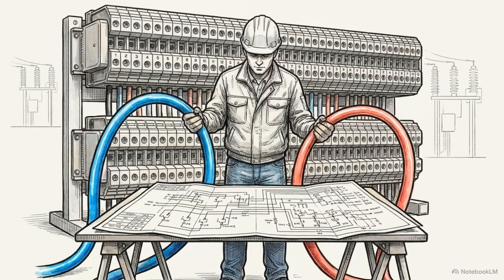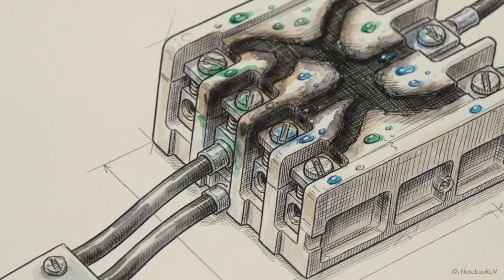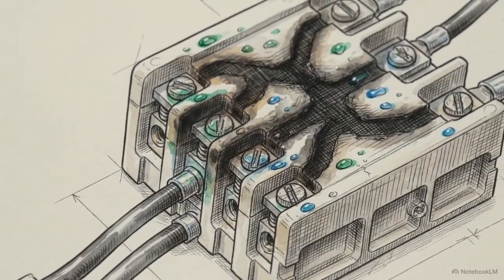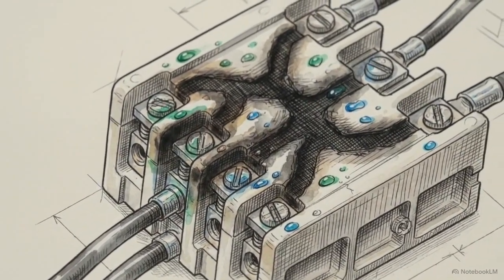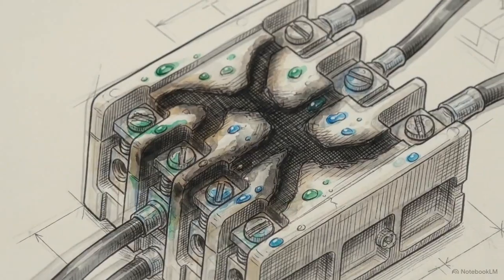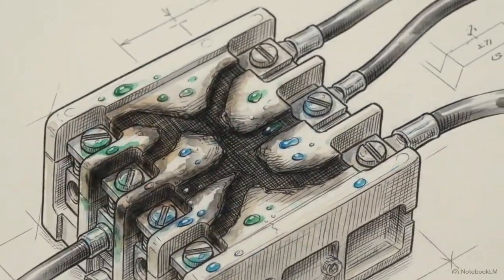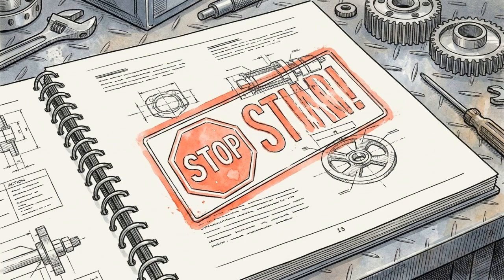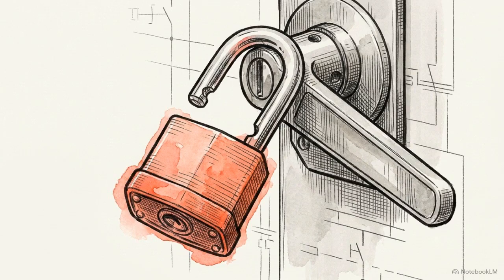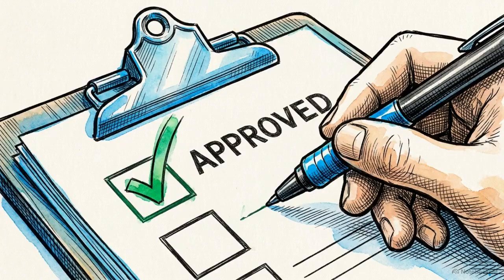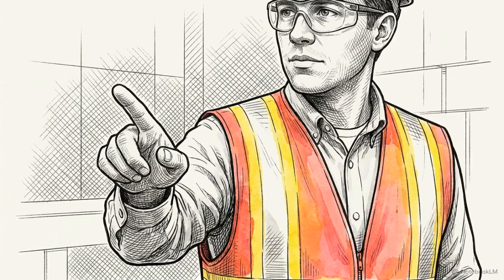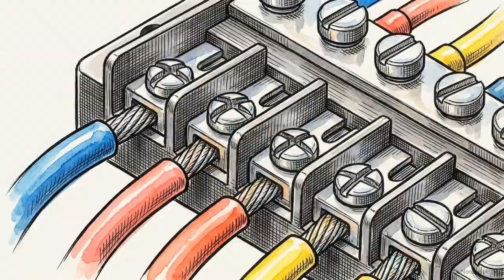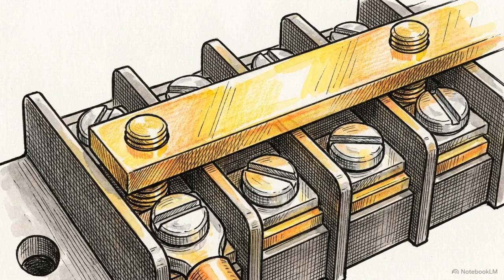If the high-voltage withstand test trips the instrument prematurely, specialists check the terminal box for moisture ingress or carbon tracking before condemning the internal insulation. The manual ends on the single most critical hold point in the commissioning process. Never leave a current transformer secondary in an unsafe state. Before the permit is cleared, a designated witness must confirm that burden cables are relanded, shorting bars are correctly configured, and terminal covers tightly secured.